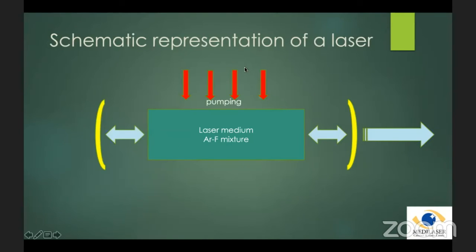So basically, your laser machine, the excimer laser that you're using, has a gas reservoir. It could be a premix of argon fluoride or two separate chambers. And from the gas reservoir, there's a laser cavity. And this chamber actually amplifies this excitation effect. So with some electrical energy that is exciting your gas mixture, there are these convex mirrors that are going to amplify this excitation effect. And then a monochromatic radiation is emitted from your laser cavity.